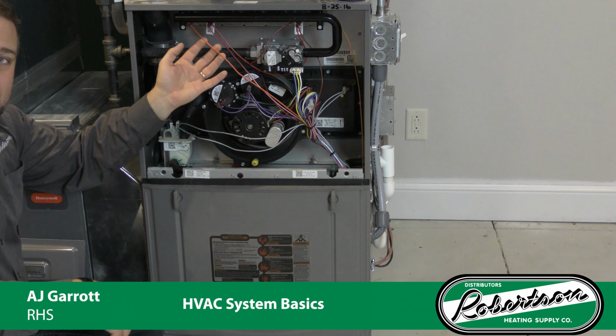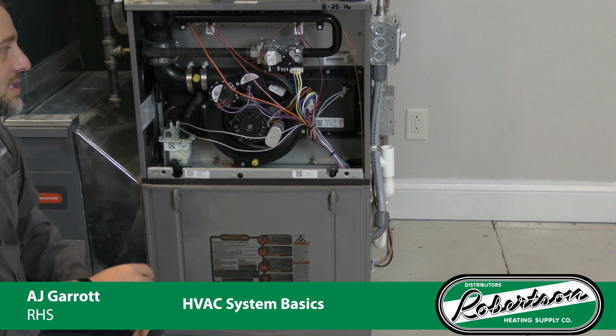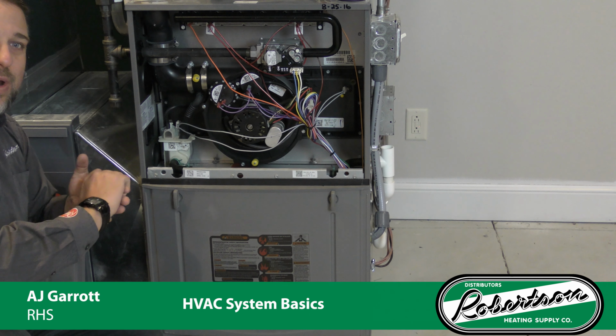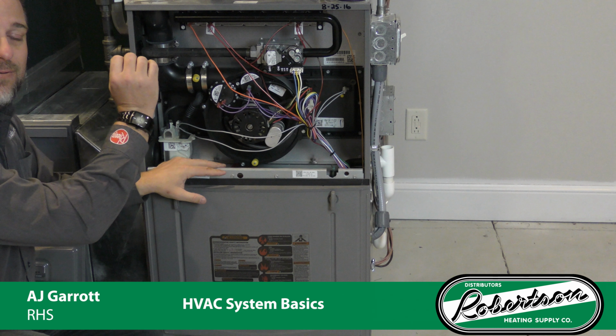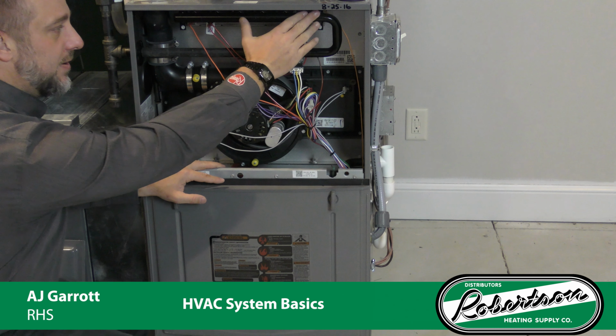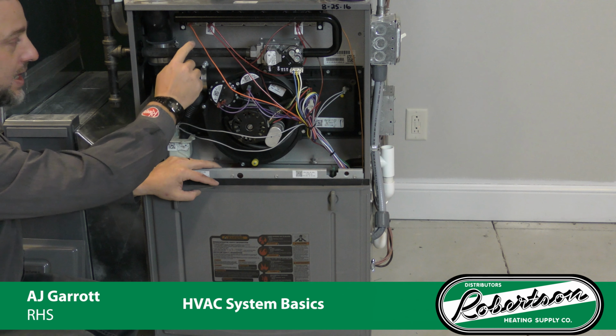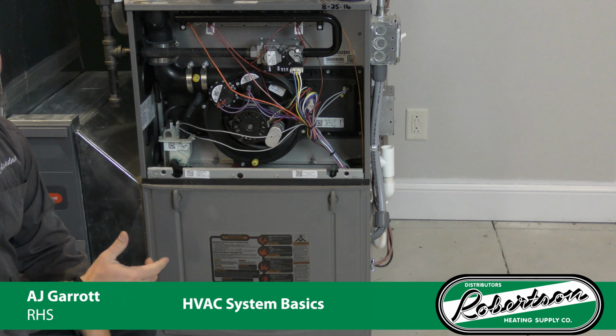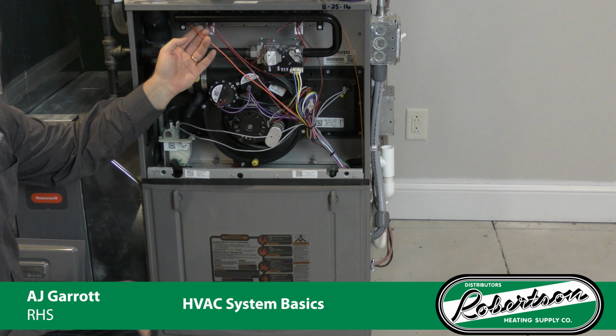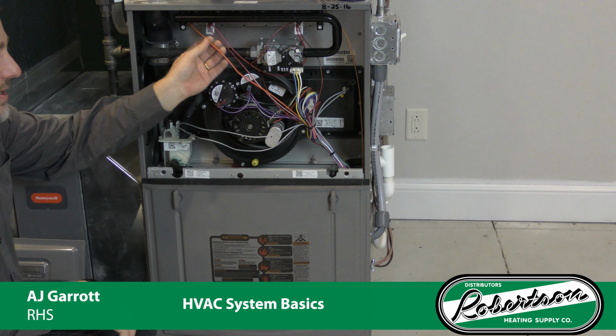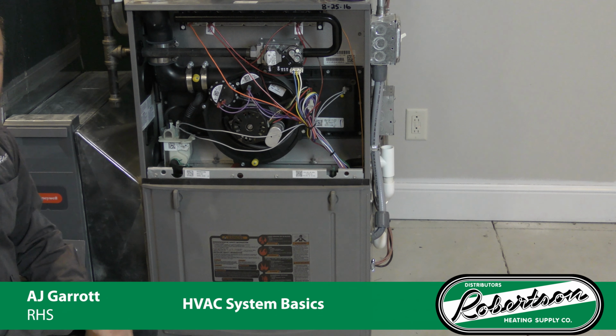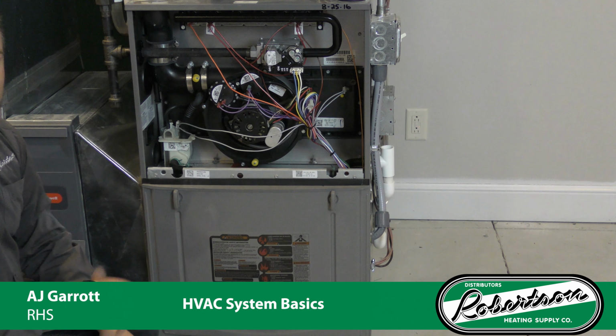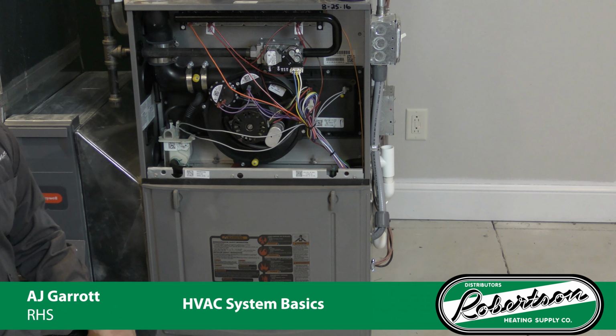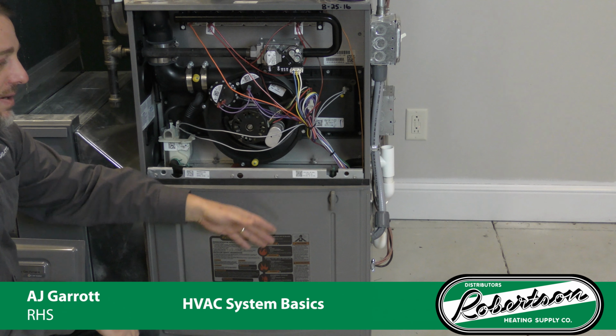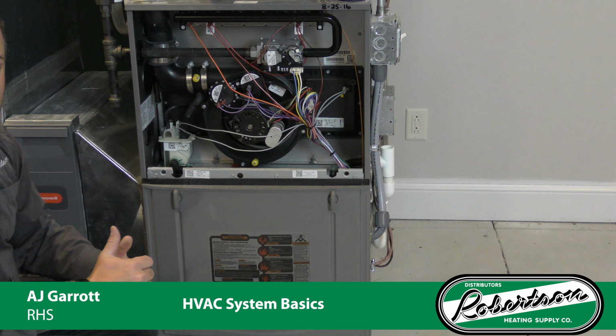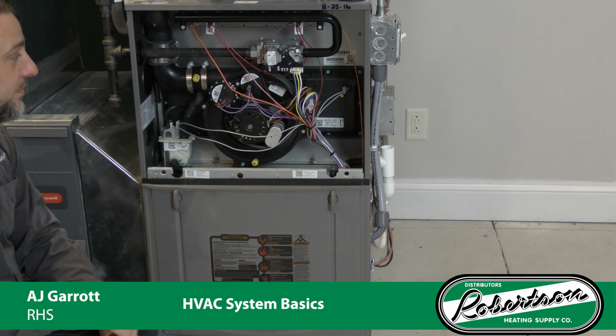Over here we have a flame sensor. The flame sensor's job is to actually make sure that we have lit the gas and we have a flame. So we light the gas on this side, it then carries across the burners and proves flame or ignition on this side to make sure every burner lit. The flame sensor runs down into the control board, and then through a process of digital, it could be a digital signal, it can be through microamps, it's actually reading back into the control board telling it we have a flame, we're safe, we're good to go.